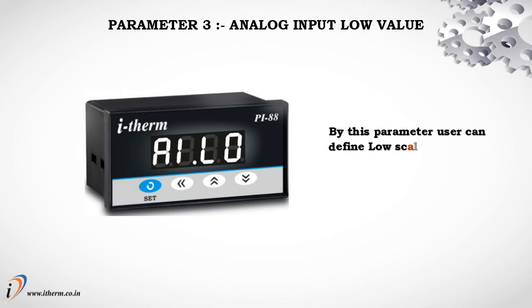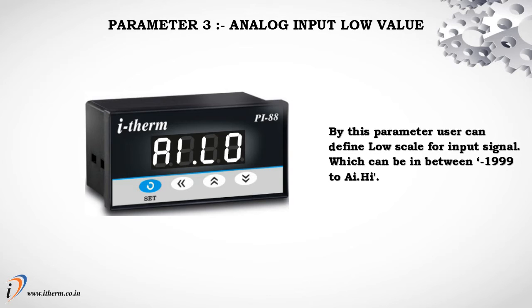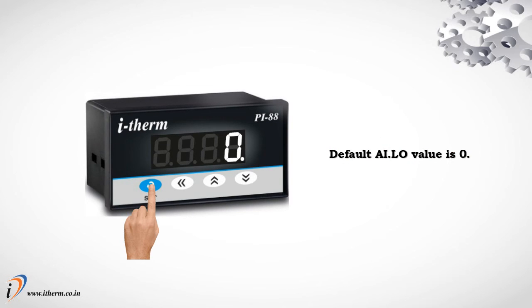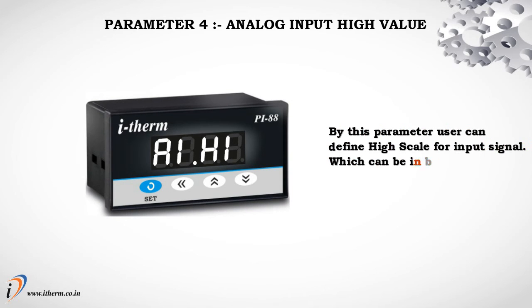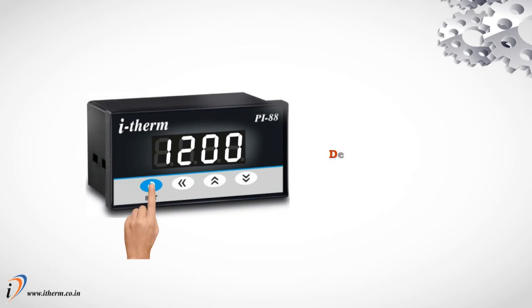Parameter 3: Analog Input Low Value. By this parameter, the user can define the low scale for the input signal, which can be between minus 1999 and the analog input high value. The default analog input low value is 0. Parameter 4: Analog Input High Value. By this parameter, the user can define the high scale for the input signal, which can be between the analog input low value and 9999. The default analog input high value is 1200.